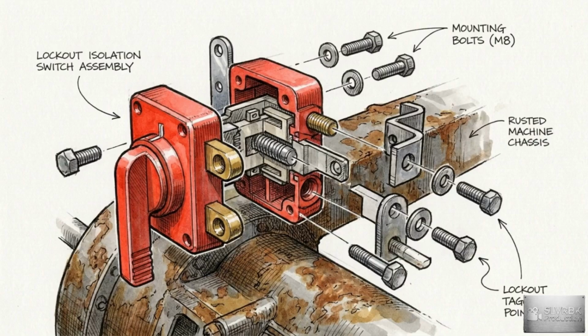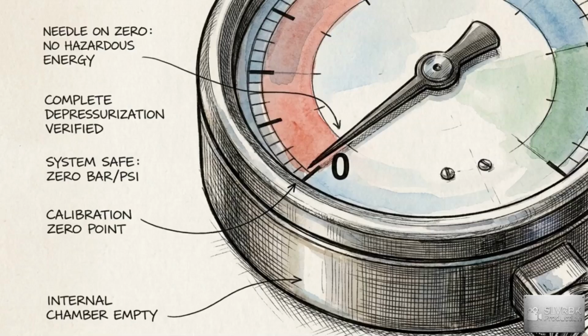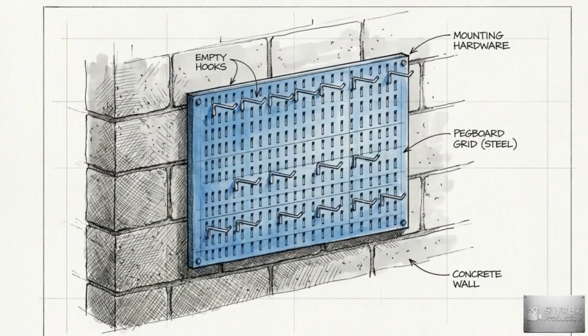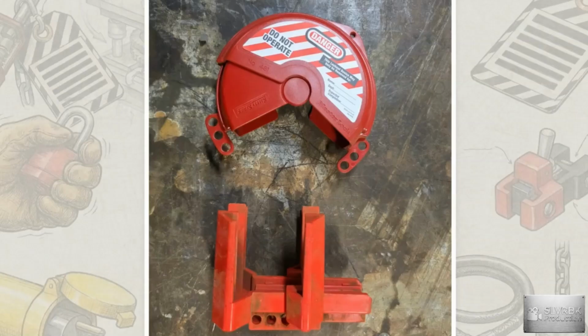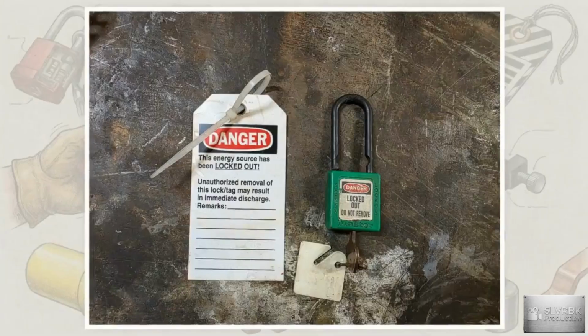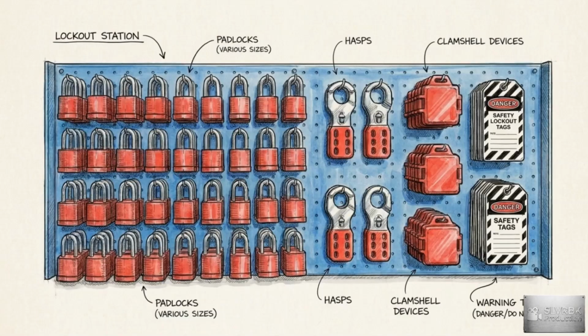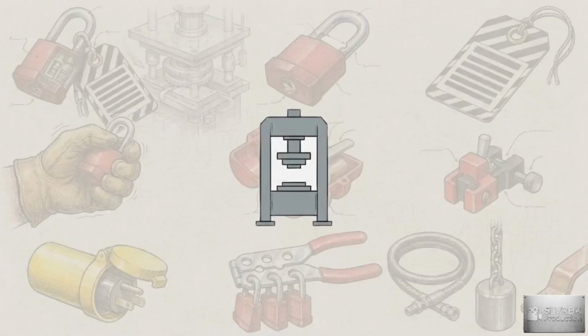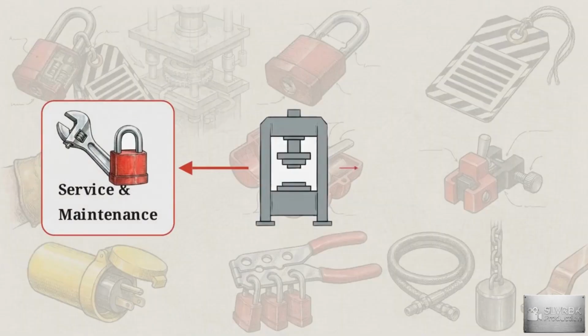Furthermore, whenever older machinery undergoes major repair, renovation, or modification, the regulations require the facility to upgrade the isolating devices so they can accept physical locks moving forward. Every component of this system serves one objective: maintaining a zero-energy state to ensure no machine part moves until it is safe. Possessing the standardized hardware, the specialized clamshells, the multi-hole gang clamps, and the 50-pound test nylon tags is only the foundation of compliance. With the physical tools understood, we have to analyze the procedural exceptions, mapping exactly when these strict rules apply during heavy maintenance and when they differ during normal production operations.